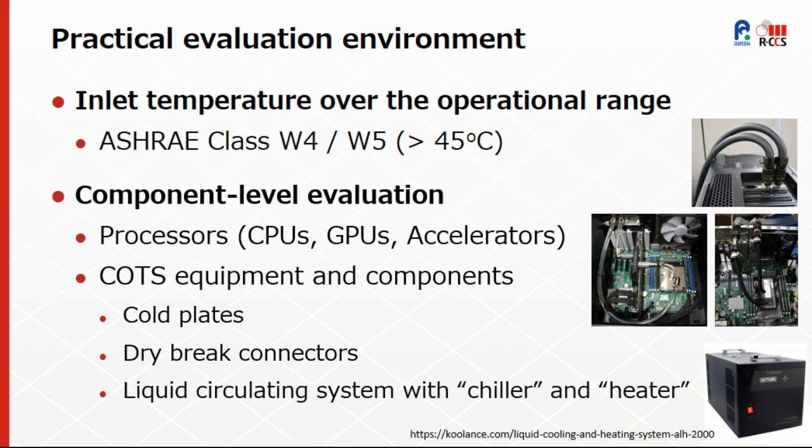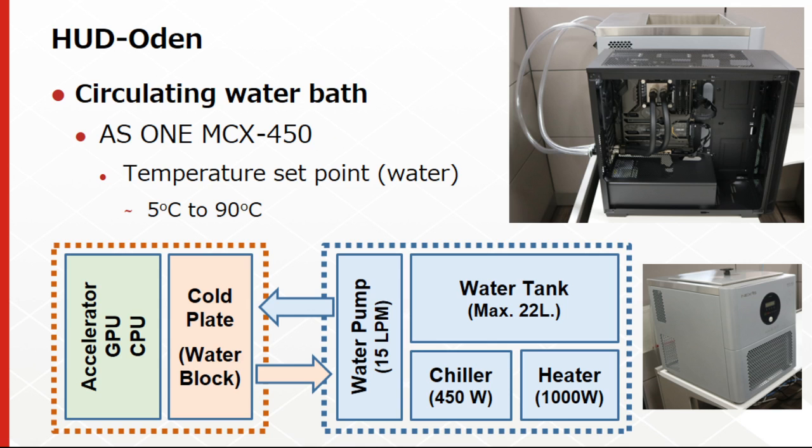The most difficult part was to find a temperature-controlled liquid circulation equipment with chiller and heater. At the time when we started this work, we could not find such equipment, and we focused on a circulating water bath used normally for in vitro experiments. We acquired the AS ONE MCX-450 with a water tank, water pump, chiller, and heater, and connected flexible hose with dry break coupling to facilitate the changing of evaluation targets.